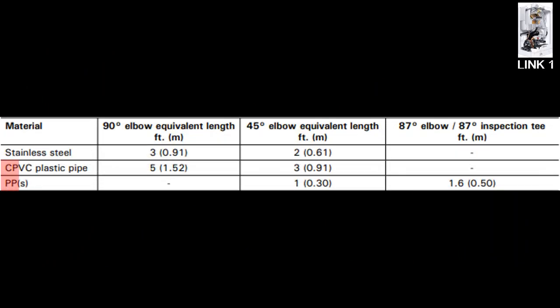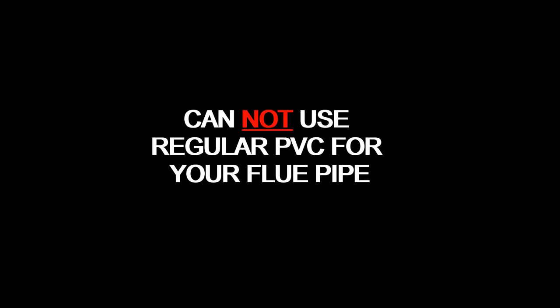If you are planning on using CPVC or PPS for your flue pipe, you must ensure that it is ULC S636 or UL 1738. Otherwise, it's not rated for the temperature of the flue gas. You cannot use regular PVC for your flue pipe.